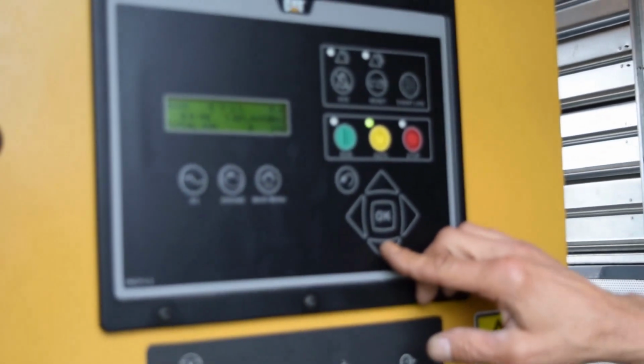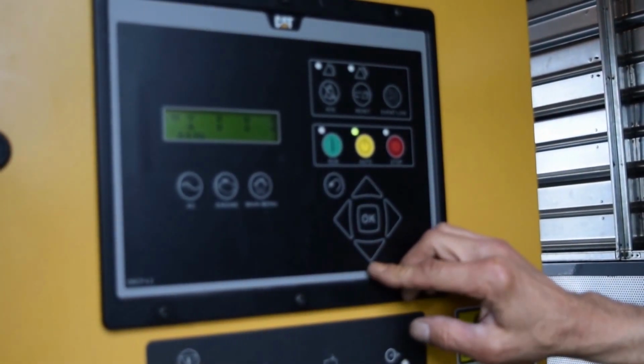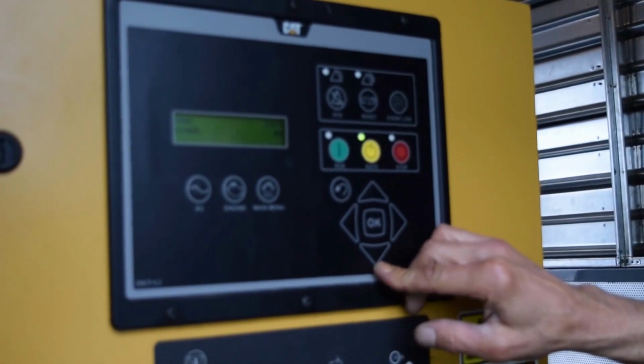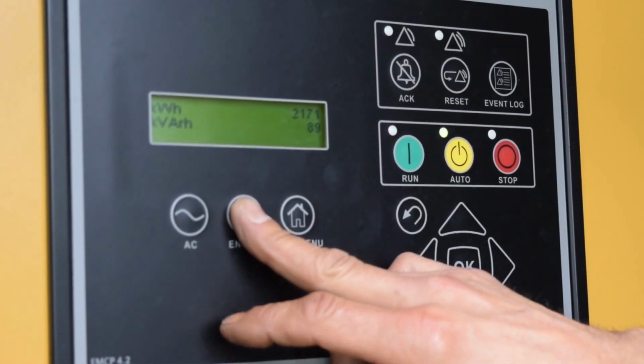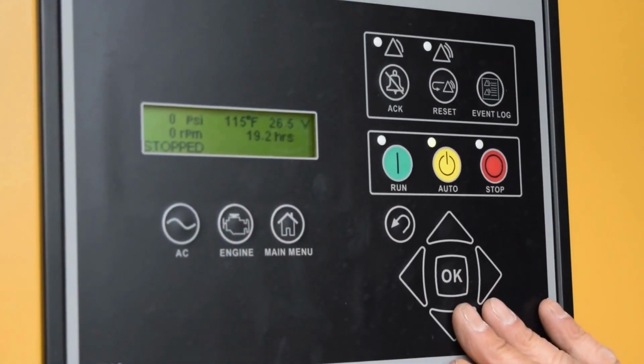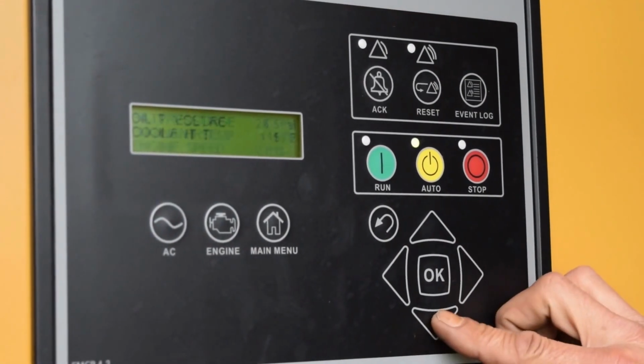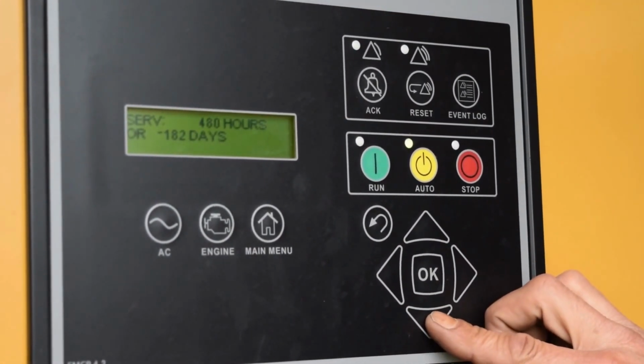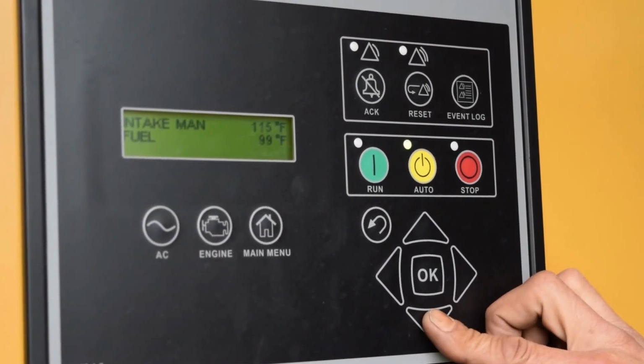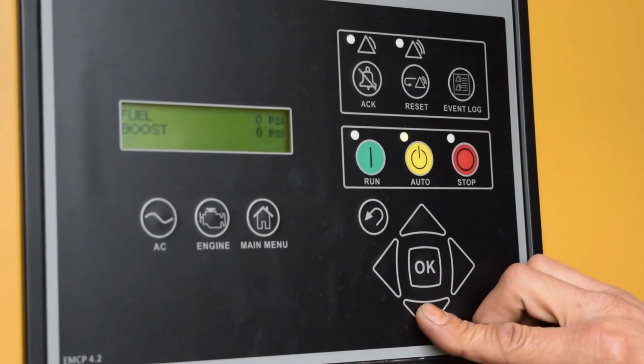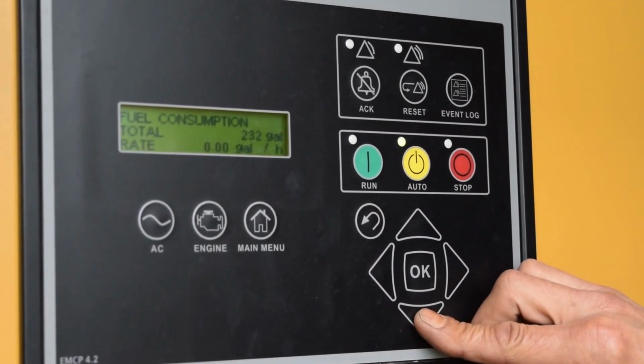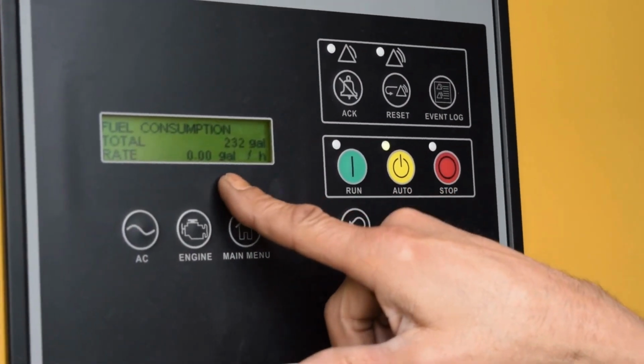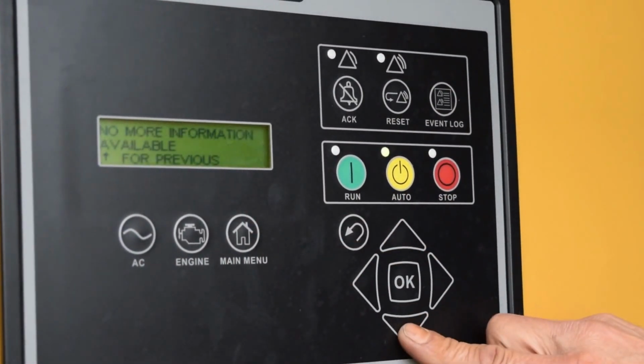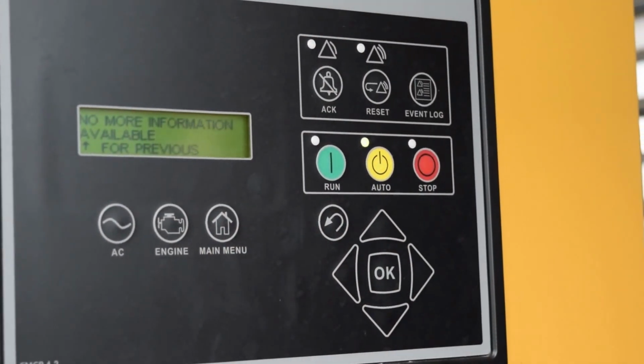On our display, you can pick your AC display, showing you all the electrical items during your run. It'll give you your volts, amps, hertz, power factor, kilowatts, kVAR, and right on up to your kilowatt hours on the generator. Same thing with your engine. It'll give you all your temperatures and pressures, and as you use the scroll buttons, you can scroll down and see the rest of the items that are in there, such as your intake manifold temperature, your fuel temperature, your fuel and your boost pressures, your total consumption to date, and your fuel rate when you're running. And when you get to the bottom, it says that's it, no more available.